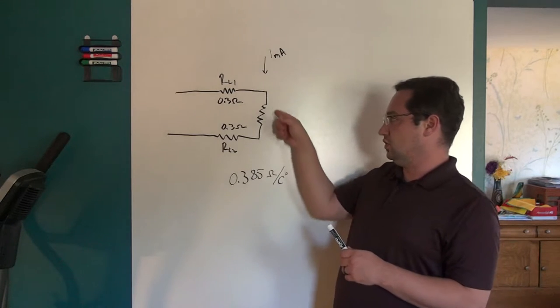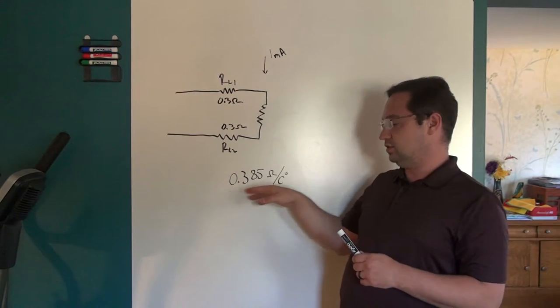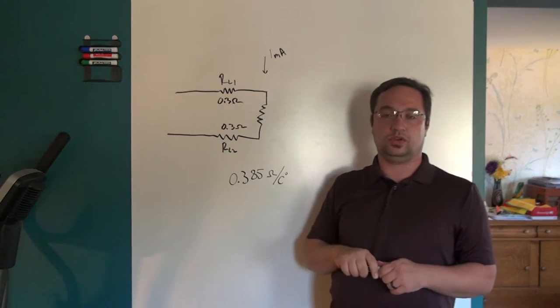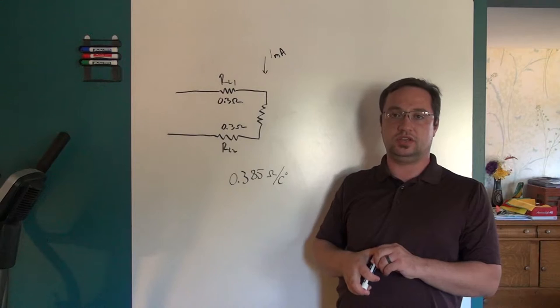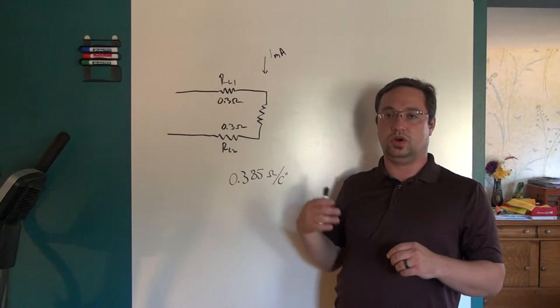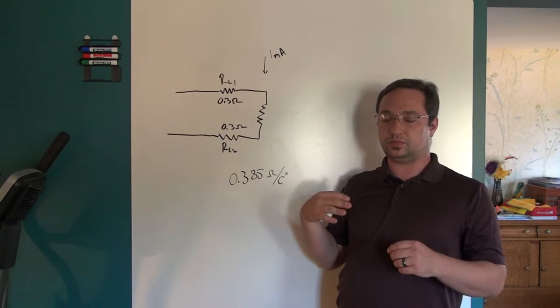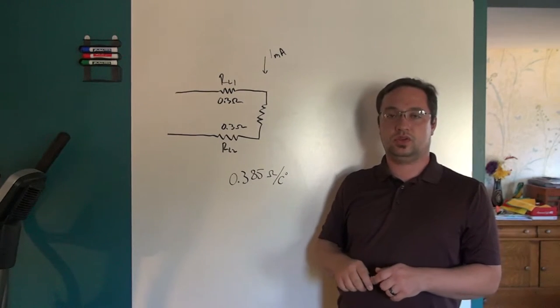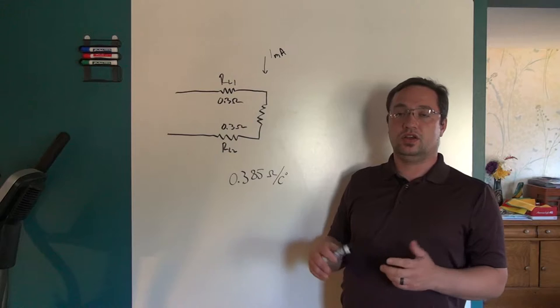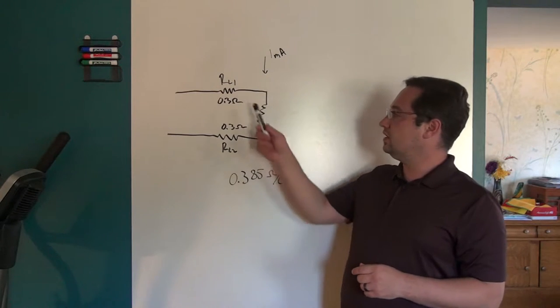The thing to be careful with is, at least my first thought was, why can't we just calibrate out these 3 tenths of an ohm? Just take your reading and subtract out the 1.6 degrees that you added in there. The problem with that is, these leads also have their own independent temperature coefficient.